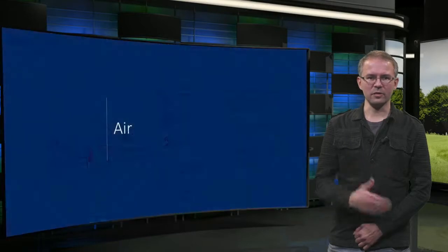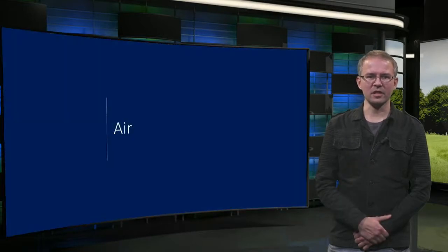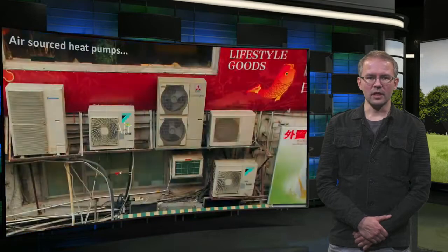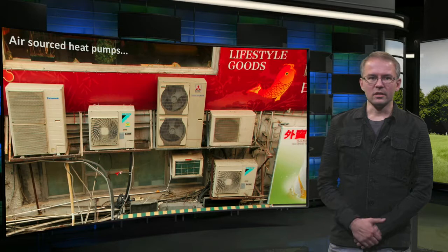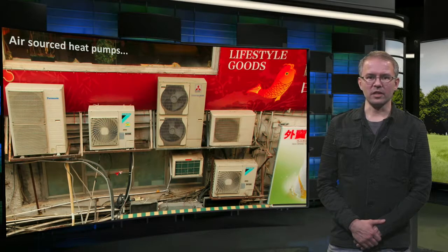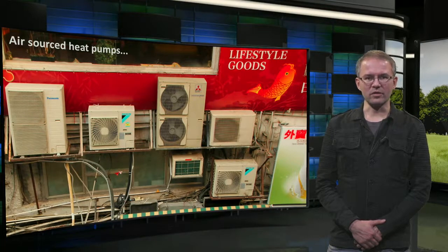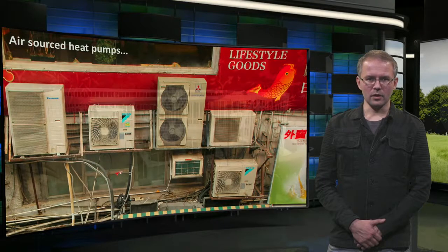Air will be the most familiar environmental source of energy, especially for cooling. In a previous lecture you learned about air conditioning or AC units. These are also known as air-sourced heat pumps because they use the outside air as a heat sink. They can also be used in reverse to heat up your building. Compared to the other sources, air-sourced heat pumps are however the noisiest and least efficient — they will use a lot more electricity for the same amount of heat or cold, and are therefore more expensive when used.